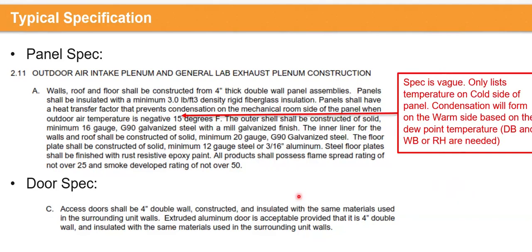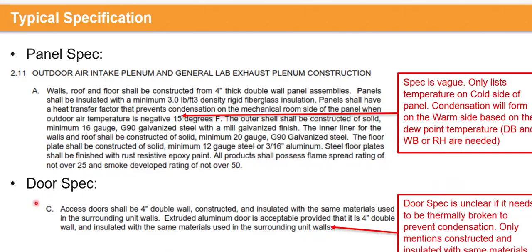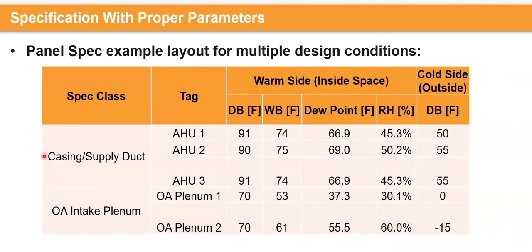Another part that is fairly overlooked would be the doors. We do not think much about it, but the framing on the doors would lead to a derate on the thermal conductivity or the heat transfer through the door frame as well, and that could lead to condensation. Based on this, we did ask for panel specs for typical operating conditions, and this is what it came up to. We're given dry bulb temperatures, which were great. We have the cold side temperatures, which were great, and we also have the relative humidities. Now, with this information, we are able to estimate what the dew point temperatures would be. So once again, if our surface temperature is above that, no condensation. Immediately the surface temperature drops below that, we would have condensation.